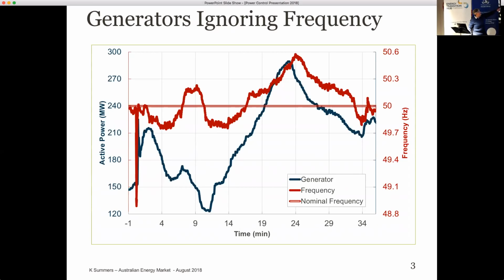Following that, we had a number of interventions from some diesel machines which pushed the frequency around. But at this point, two large machines in an islanded area decided they were going to provide ancillary services, and they drove the frequency from the boundary of 49.85 straight through to nearly 50.6 at the top of the chart. Now that is a control system that really doesn't know what it's doing.